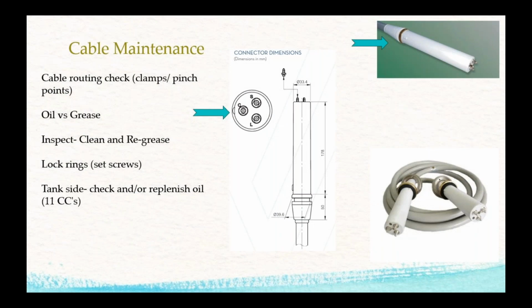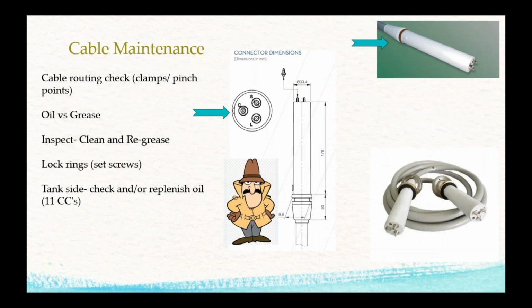Cable maintenance, another important thing. High voltage is going through these cables several times a day. So we want to pull these out of the X-ray tube and inspect them for any burn marks, frayed cables, bad insulation or anything. And then we also have a silicone grease that we coat this with. This is known as a candlestick for obvious reasons. You've got 3 pins.